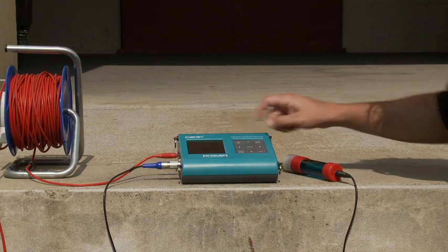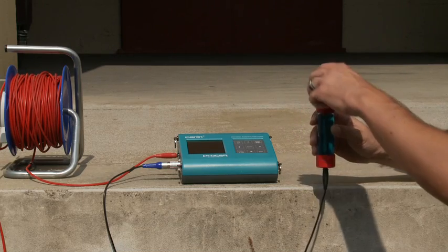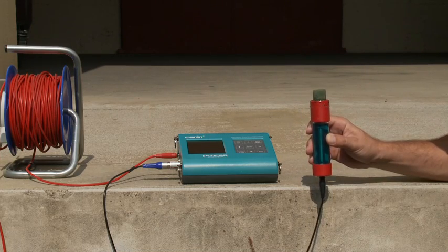Before real tests begin, a functional check is recommended. The probes should provide a stable value close to 0 when they are held in the air and a Canin Plus instrument is connected to Earth. It is also a good idea to make measurements on areas that are clearly damaged and compare them with measurements on areas that are clearly intact.